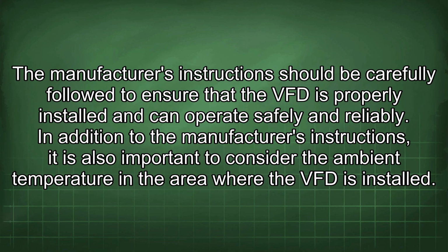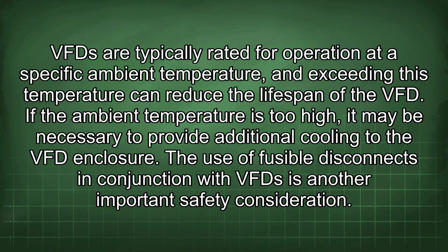The manufacturer's instructions should be carefully followed to ensure that the VFD is properly installed and can operate safely and reliably. In addition to the manufacturer's instructions, it is also important to consider the ambient temperature in the area where the VFD is installed. VFDs are typically rated for operation at a specific ambient temperature, and exceeding this temperature can reduce the lifespan of the VFD. If the ambient temperature is too high, it may be necessary to provide additional cooling to the VFD enclosure.